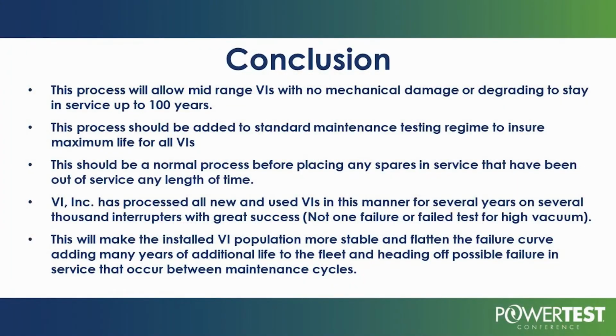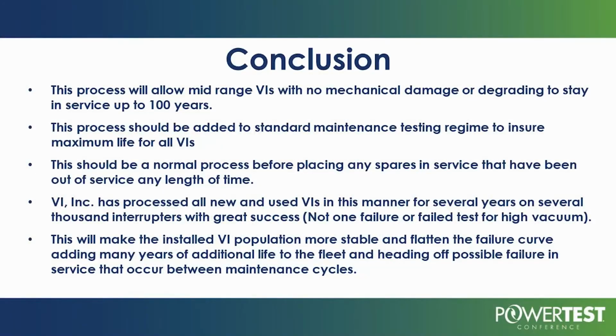Condition the interrupters at every opportunity, and you will be getting the most benefit you can for your customer, client, and for the user. The conclusion: this process allows you to keep interrupters that are in the mid-range without mechanical damage in the mid-range for 100 years or longer. This process should be added to standard maintenance testing to ensure maximum life for the VIs. That's a benefit you can bring to your customer. It's something that you can do that can actually help them. This should be a normal process before putting any spares or breakers back in service that have been out of service for any length of time.